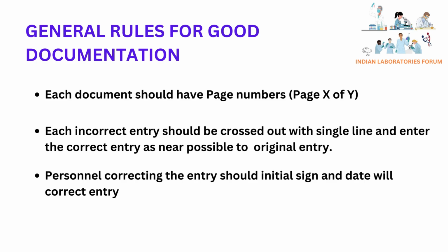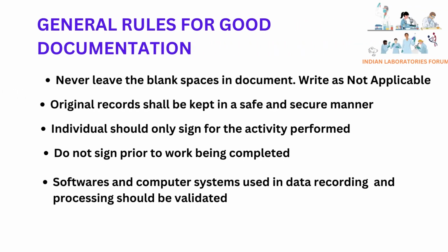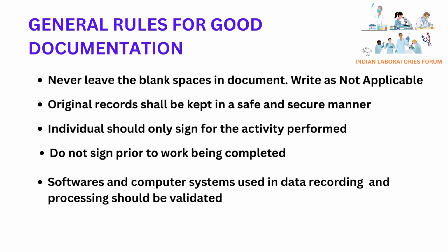Each incorrect entry should be crossed out with a single line, and the correct entry entered as near as possible to the original entry. Personnel correcting the entry should initial, sign, and date, and enter the correct entry. Never leave blank spaces in a document. Write as not applicable. Original records shall be kept in a safe and secure manner. An individual should only sign for the activity performed. Do not sign prior to work being completed.